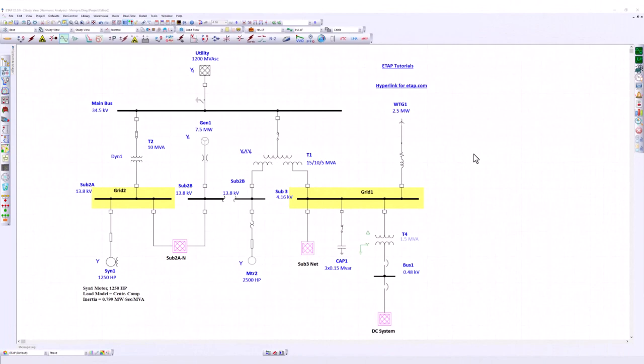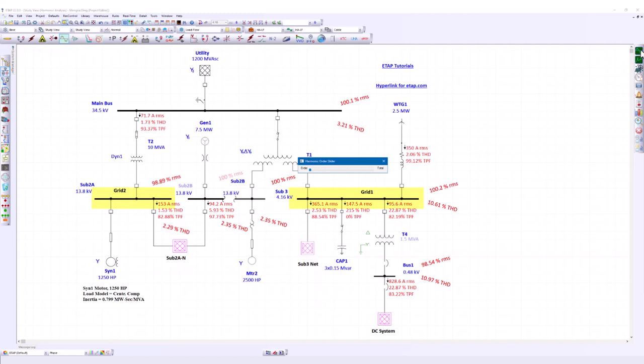To perform the harmonic load flow calculation, let's click on the first button, Run Harmonic Load Flow, in the Harmonic Module toolbar. After the calculation is completed, you will notice a harmonic order slider pops up. The first point in the slider is for total. Based on the name, you will be able to see the total harmonic voltage distortion and the corresponding RMS for every bus, and also the total harmonic distortion for current and RMS values for each branch. Worth mentioning here is that we added the total power factor for all the branches. That means the power factor you read when the slider shows total considers all the harmonics.